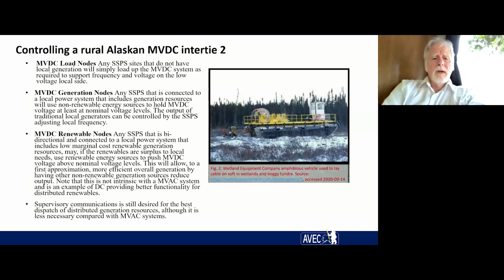Control of those nodes becomes a lot simpler because it's managed just by voltage on the distribution line. If you've got surplus power, you start pushing the voltage high. That will back off high-cost power sources, and if it goes too high, the generation sources back off. So yes, there is some control, but intrinsically it's a stable system, and you can apply controls over the top of that to take care of short-term issues.